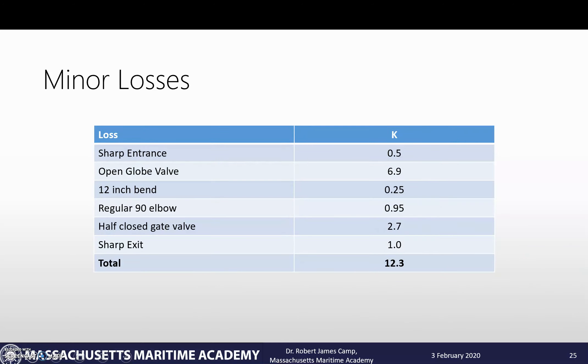Just to sum up what do we have: sharp entrance of 0.5, open globe of 6.9, bend radius of 0.25, regular 90 degree elbow of 0.95, half closed gate valve of 2.7, sharp exit of 1.0. That gives us a total of 12.3 for the minor losses.